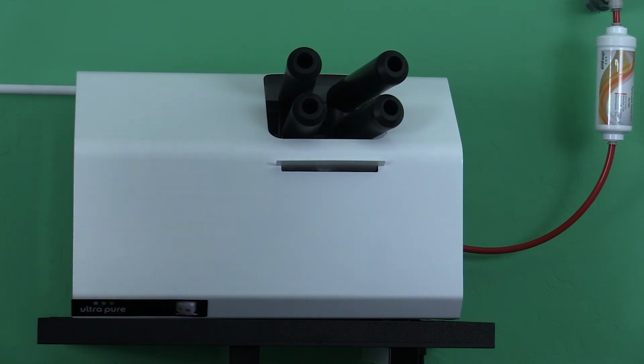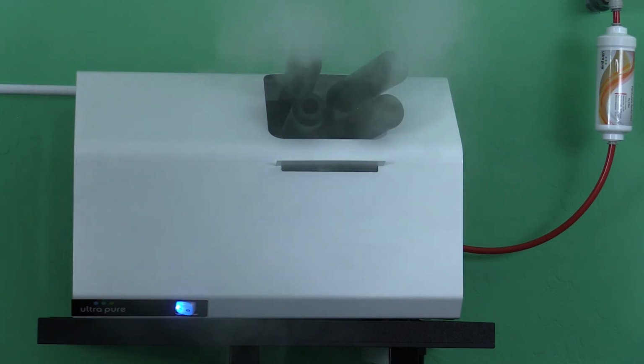The other thing to keep in mind: if you are running this humidifier with a BAS signal or a BMS 0 to 10, 2 to 10, or even 4 to 20, this proportional dynamic mode does not work. So leave that dynamic mode off if you're running a BMS signal. As you can see now, with that number 8 switch on, we're only firing the top row of transducers. The bottom row is not going to be firing because we're within that hysteresis of what we set.